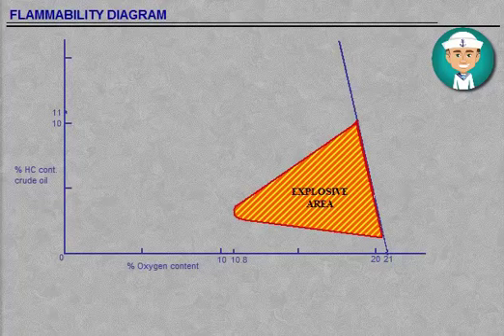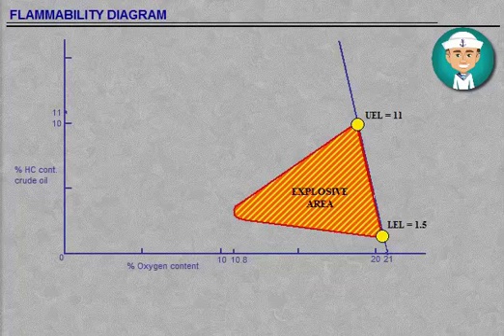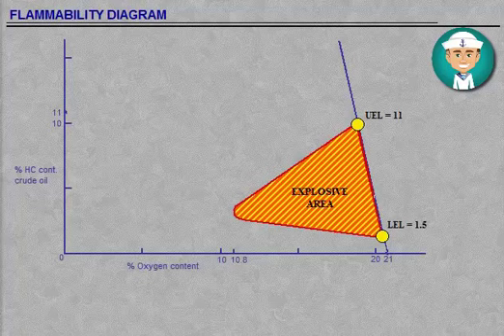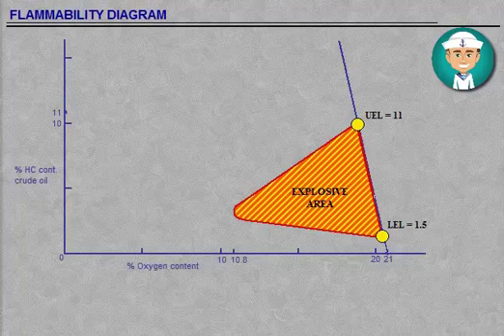The example flammable diagram is for hydrocarbon gas above crude oil where the UEL is 11% and the LEL is 1.5%. The left side of the diagram, vertical axis, gives the hydrocarbon gas value. The bottom line of the diagram, horizontal axis, represents the oxygen content from 0 to 21%.